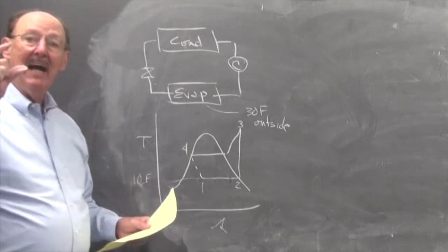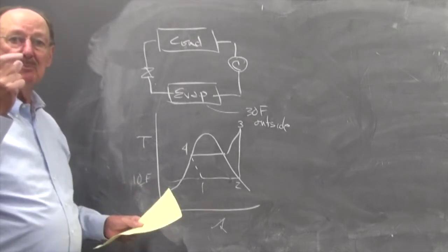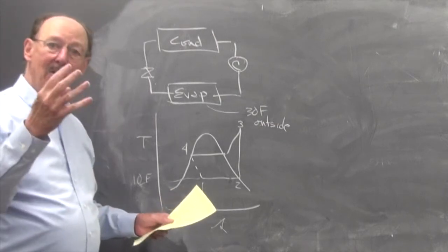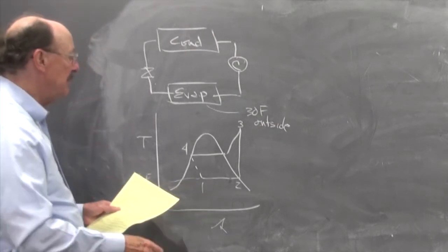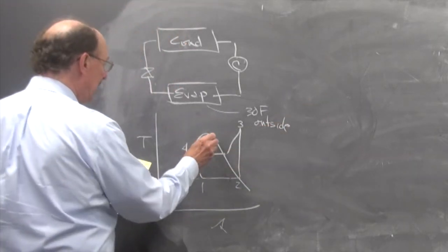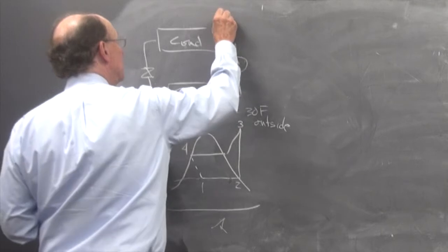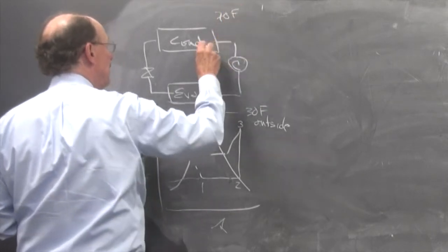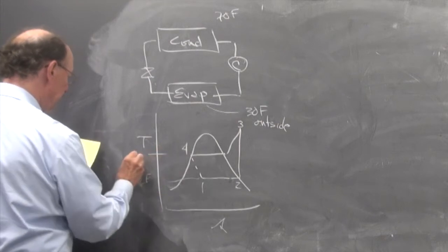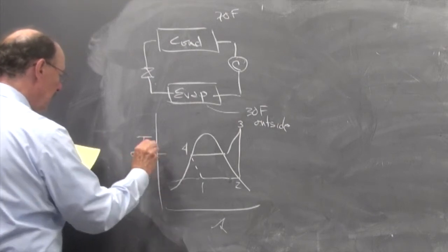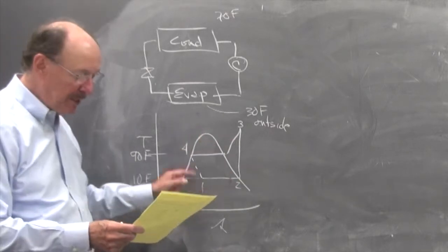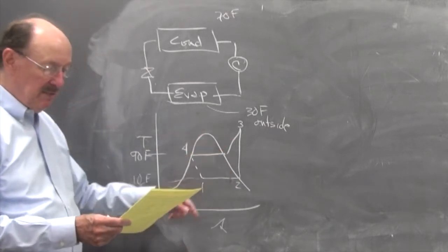So I have to have a 20-degree temperature difference between the fluid inside the heat exchanger and the air outside the heat exchanger. Similarly, if the inside air temperature is 70 degrees Fahrenheit, then the condenser has to be at 90 degrees. So that establishes the pressure requirements for this.